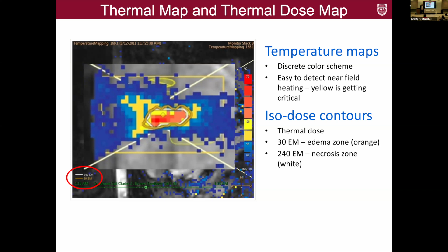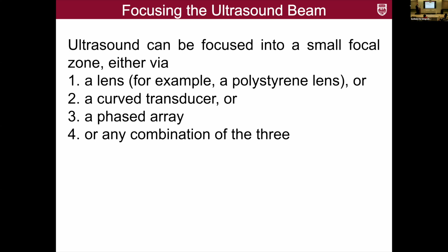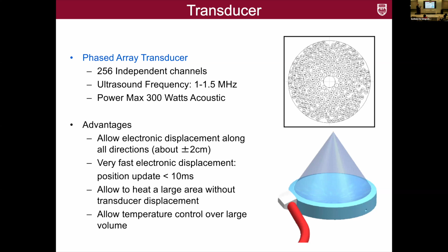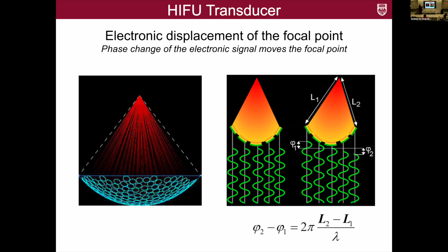The ultrasound beam can be focused in a small focal zone, either by using a lens, a curved array transducer, a phased array transducer, or any combination of the three. This is the question that you were asking, so how does it work? And this is shown here. So there's the ultrasound system. These are 256 small transducer elements, and you can steer them independently and treat the tissue by applying ultrasound pulses. We can use an electronic displacement and fast electronic switching to activate one of these elements. And then we can apply a phase difference of the ultrasound pulses, and we successfully can steer the ultrasound beam in the tissue with all these different elements that you can see here.